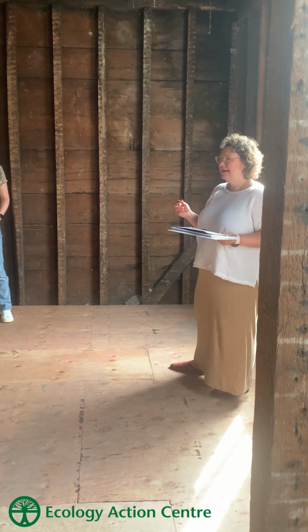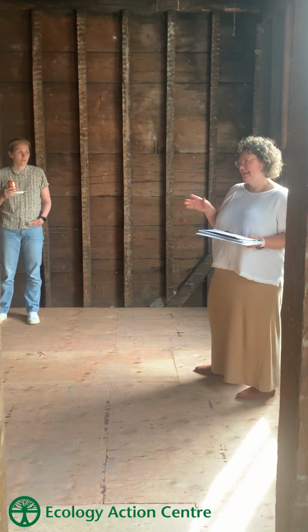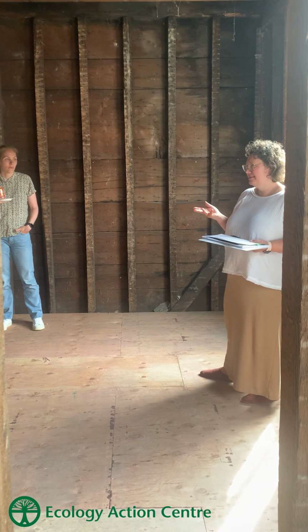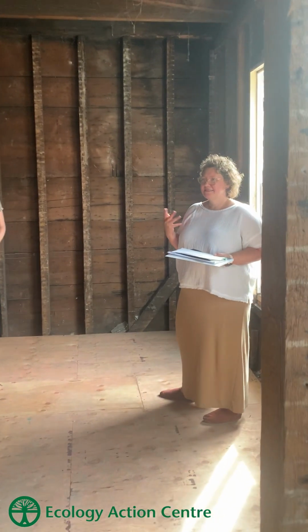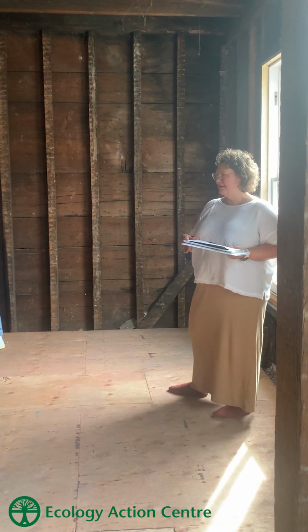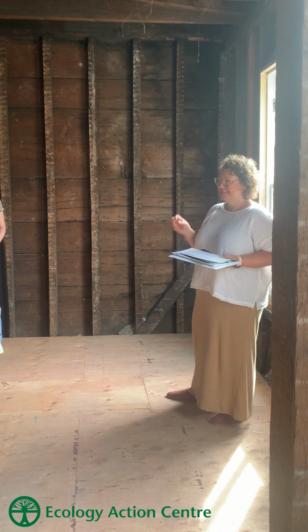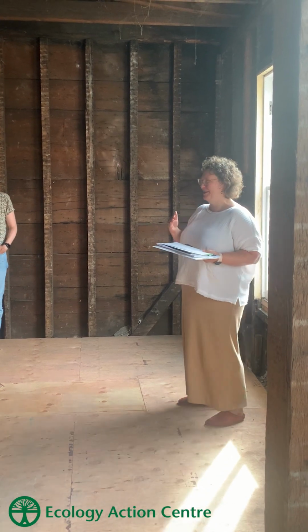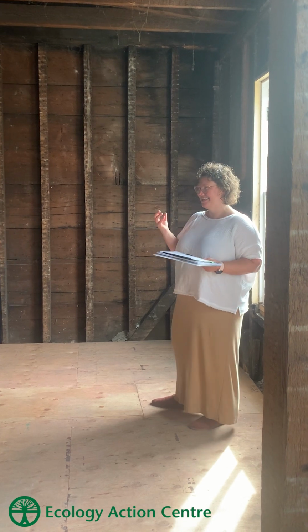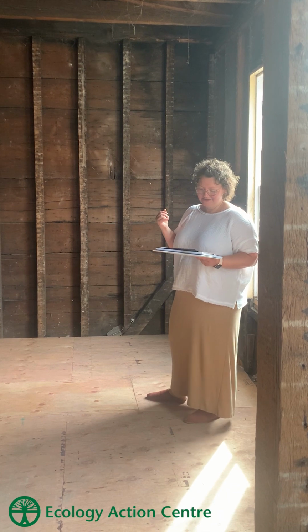It's just bad. A new build regular house, if your builder's relatively conscientious, might be like a 3. An R2000 house is 1.5. And a passive house is aiming for 0.6 air changes per hour. Passive house retrofit gives us a little bit of help, and we only have to aim for 1. That's still a long way from 24. So starting with air tightness is our fundamental move, but it's not going to be the only thing that we can do to reach our targets.